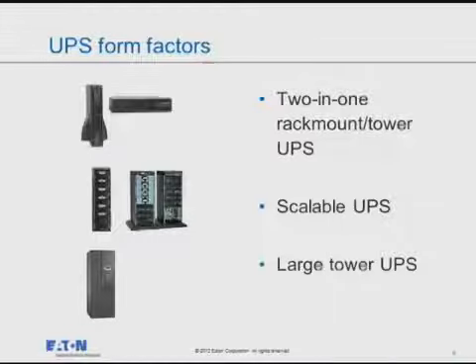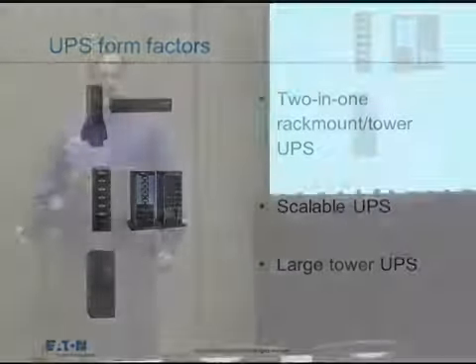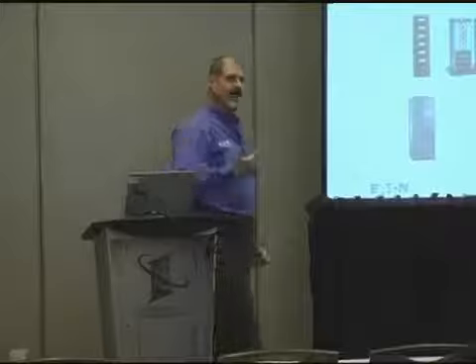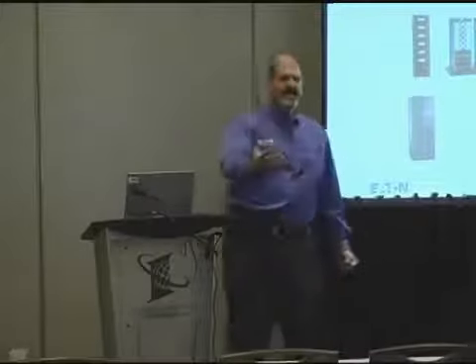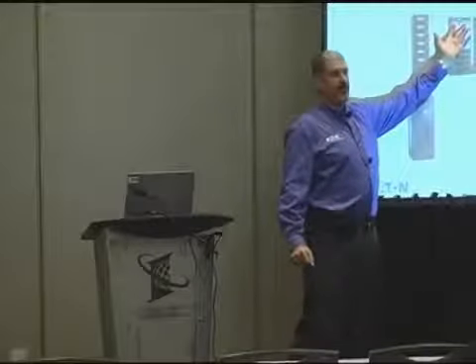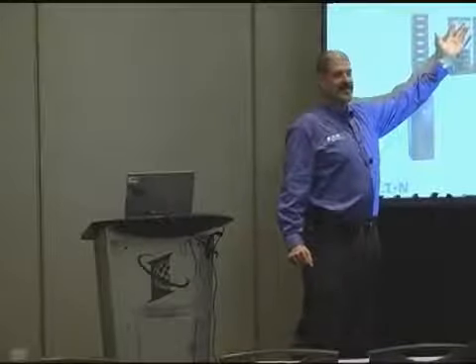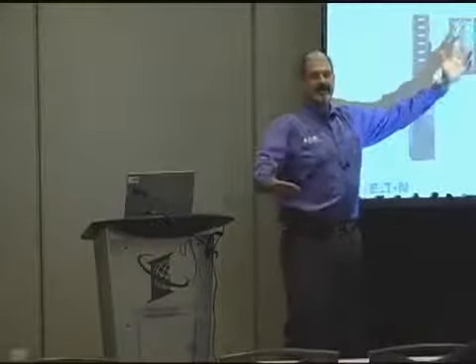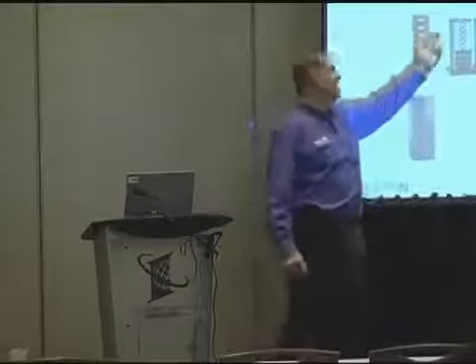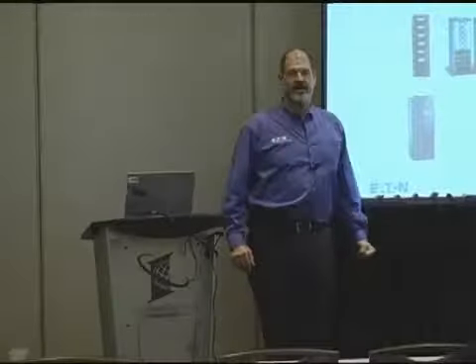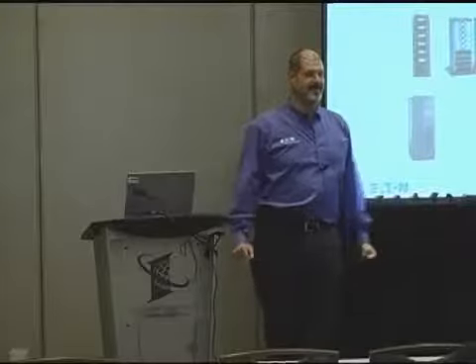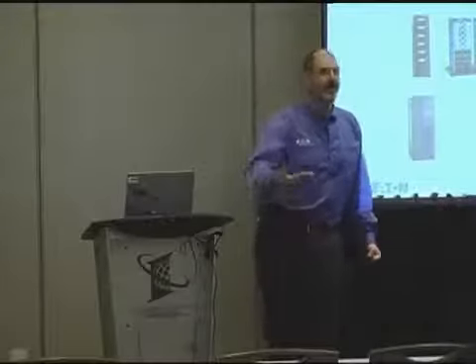Yesterday, we spent the whole hour talking about scalability and scalable UPS systems, right? But here we're talking about pay as you grow. If my load today is a 3 kilowatt requirement, I can put a 3 kilowatt power module into an expandable chassis. As my loads expand, as I need another 3 kilowatts, I can add another 3 kilowatt power module and create a 6 kilowatt UPS, or a 9 kilowatt, or a 12 kilowatt.